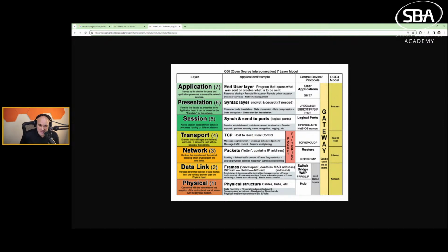Because we have services in BACnet that are things like read property, and they're a confirmed request or a complex request, and they require an acknowledgement. So how do we actually do a receive acknowledgement and send stuff back if we are using a connectionless protocol? And that's where we actually get up into the application layer, and that's where the BACnet virtual link and NPDUs and APDUs come into play, which we'll talk more about in just a little bit. But that's a brief primer when I say layers 1 through 4, kind of gives you a high level.